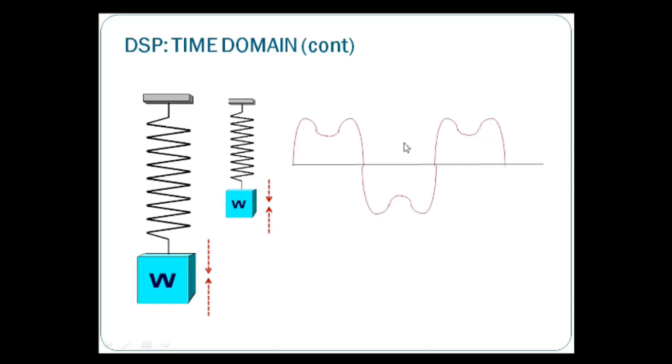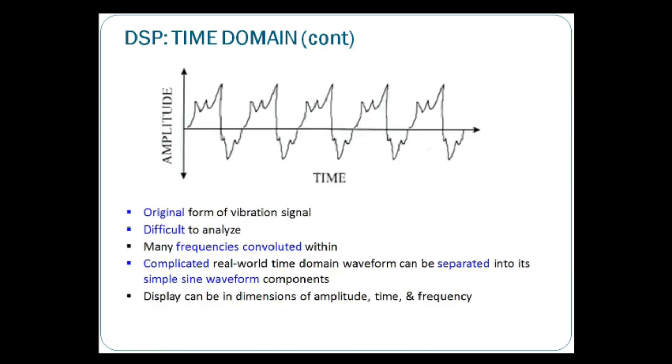So if you have a system that is vibrating, or its motion is basically convoluted, or what we call superimposed, by two different frequencies, the time waveform or the vibration signal you will see is something like this, giving you high frequency components and low frequency components superimposed together.